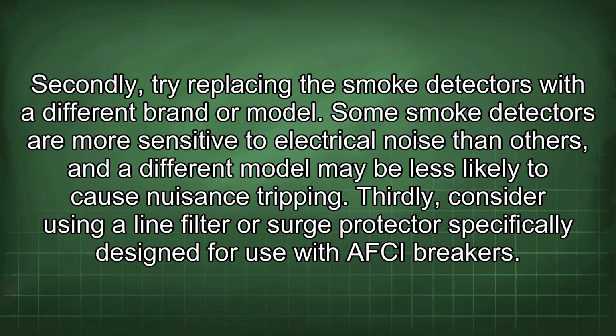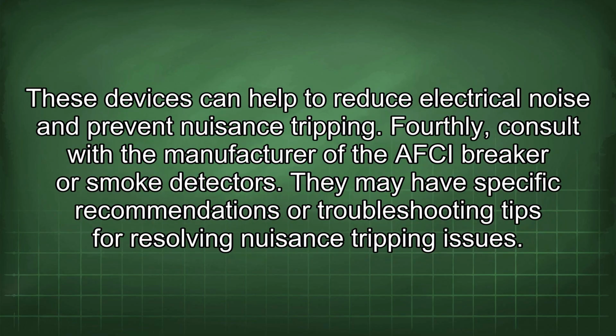Secondly, try replacing the smoke detectors with a different brand or model. Some smoke detectors are more sensitive to electrical noise than others, and a different model may be less likely to cause nuisance tripping. Thirdly, consider using a line filter or surge protector specifically designed for use with AFCI breakers. These devices can help to reduce electrical noise and prevent nuisance tripping. Fourthly, consult with the manufacturer of the AFCI breaker or smoke detectors. They may have specific recommendations or troubleshooting tips for resolving nuisance tripping issues.